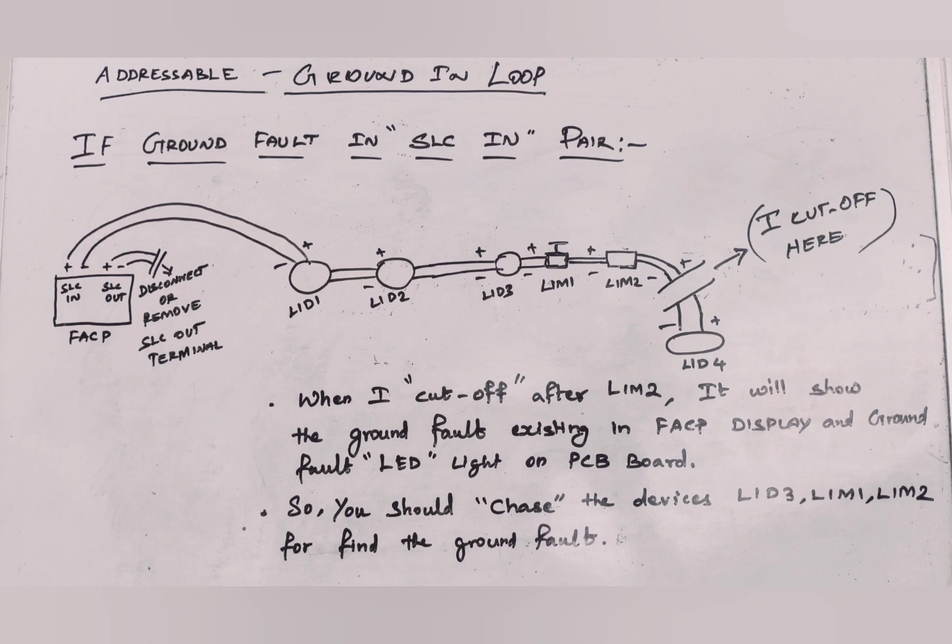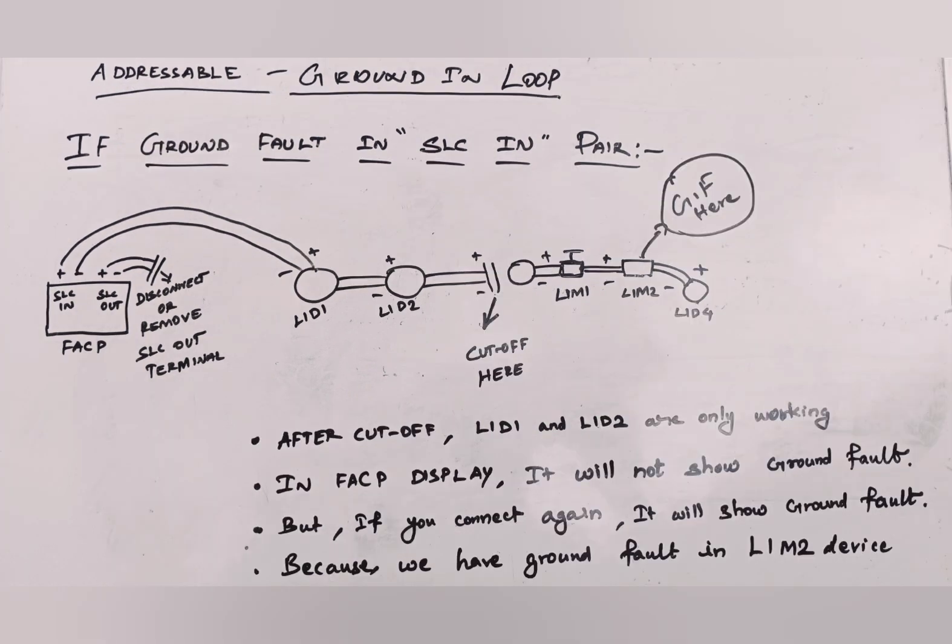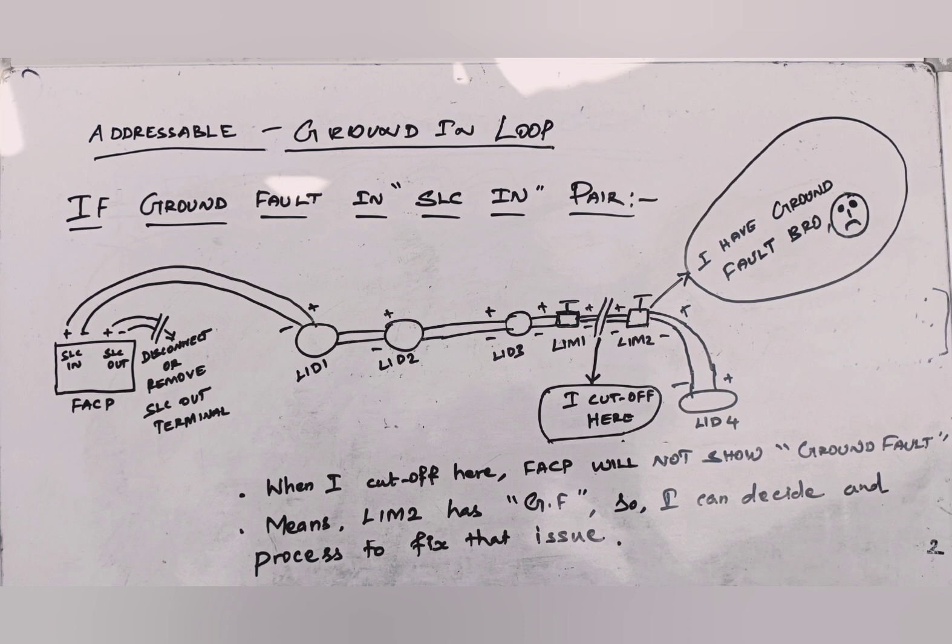When I am cutting off the continuity after L1M1, the FACP control panel will not show the ground fault, which means L1M2 is the culprit. So we need to troubleshoot over there. Maybe it has a ground fault with the back box or with conduit.